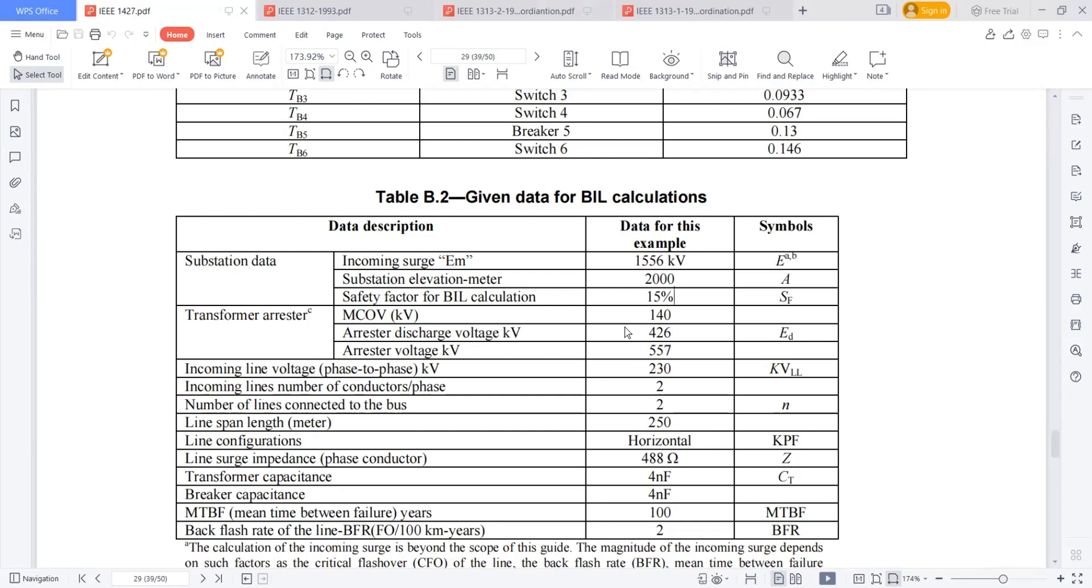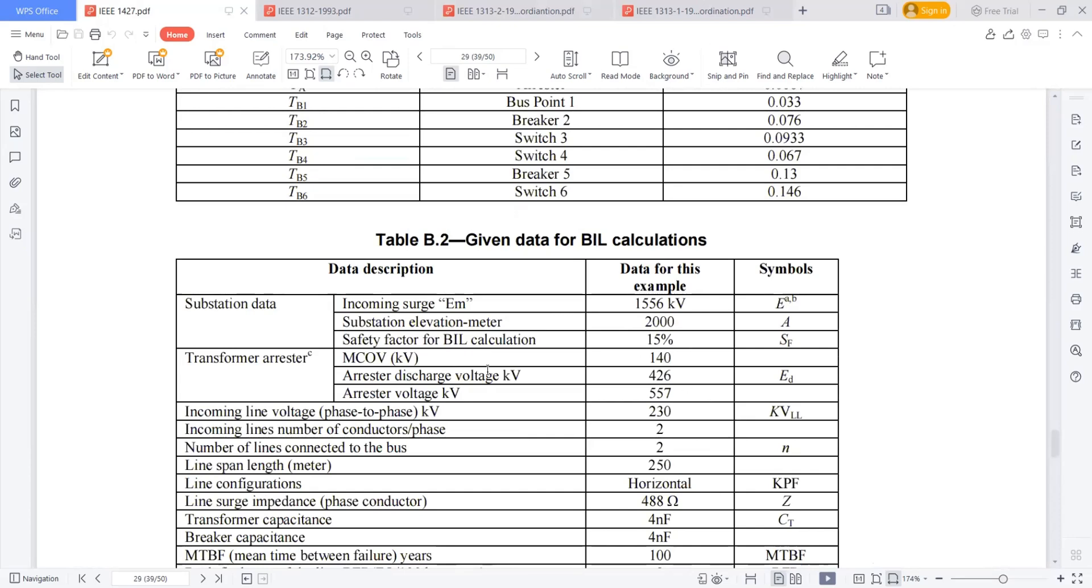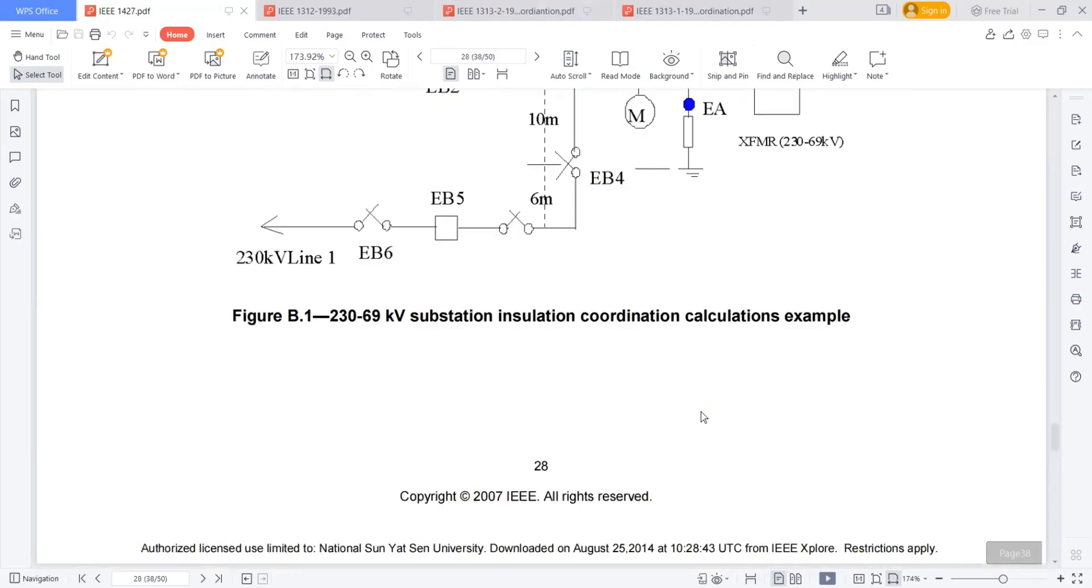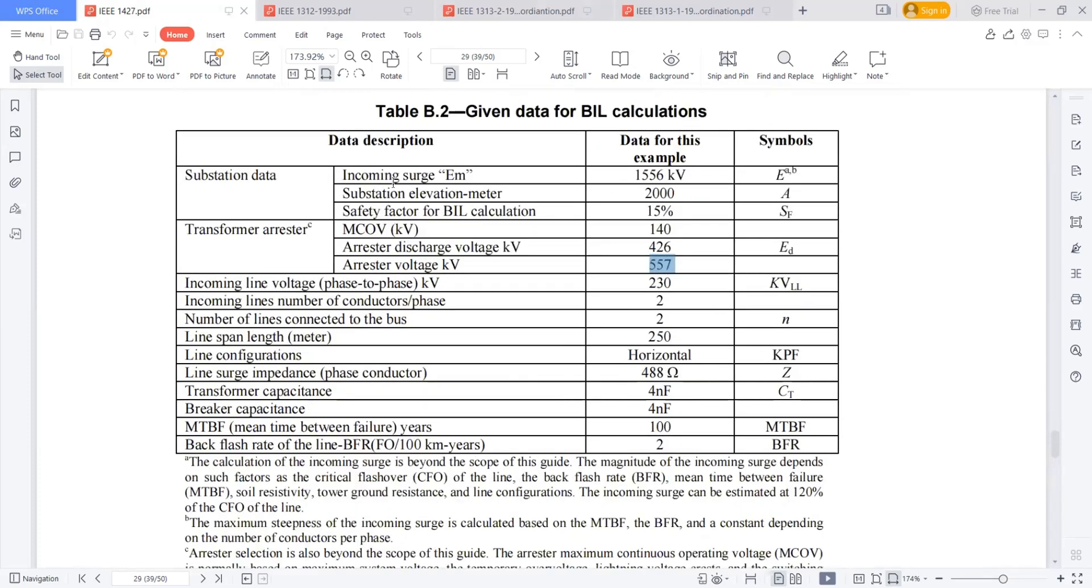Like we have done the calculation for the lightning arrestor, right? Like for the 230 kV system, just to calculate the phase to ground, 230 by root 3, 132.79 into 1.1, which is 146. So taking into solidly grounding factor, all these things, he selected 140 kV. And arrestor discharge voltage, what is the discharge voltage of this arrestor? Suppose it is 426 kilovolts. This is the discharge voltage of the arrestor. Arrestor voltage is 557. This is a breakdown voltage. These are the things I can get from the manufacturer.